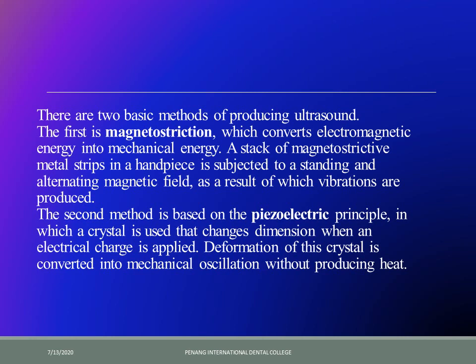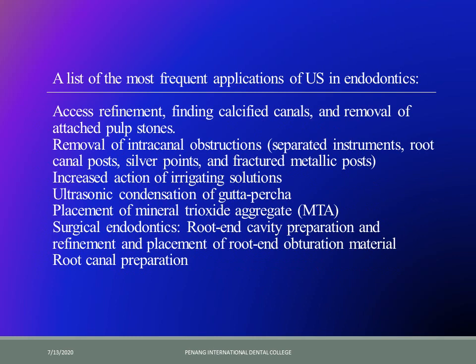In the piezoelectric system, a crystal inside the handpiece changes dimension when electricity is applied, and this deformation is converted into mechanical oscillation without producing heat. In the magnetostrictive system, heat is generated which can cause trauma to hard and soft tissues — this is why the piezoelectric is much more beneficial.